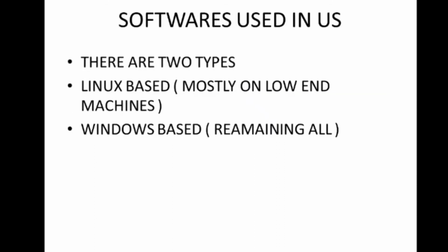You were asking me about what software is used in ultrasound. Basically there are two kinds: Linux based software and Windows based software, that is, Linux based ultrasound and Windows based ultrasound. Linux based ultrasound machines are mostly not available nowadays. They have been outdated. Nowadays we have only Windows based ultrasound.